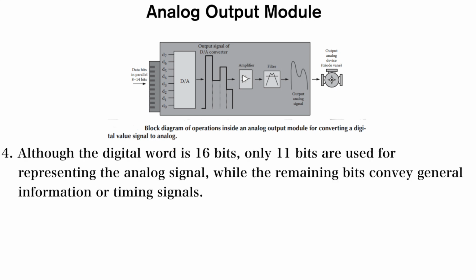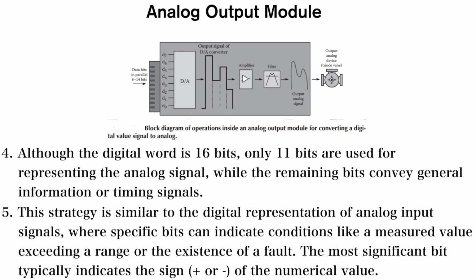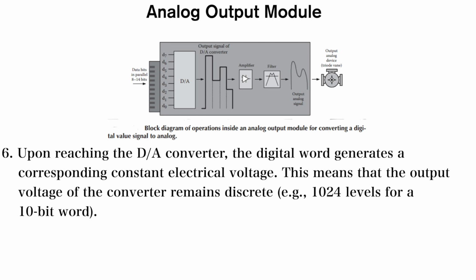Although the digital word is 16 bits, only 11 bits are used for representing the analog signal, while the remaining bits are used to convey general information or for timing signals. This strategy is similar to the digital representation of analog input signals, where specific bits can indicate conditions like a measured value exceeding a range or the existence of a fault. The most significant bit typically indicates the sign, positive or negative, of the numerical value. Next, upon reaching the digital to analog converter, the digital word generates a corresponding constant electric voltage.